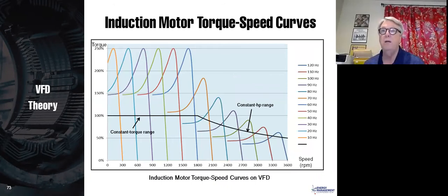Now, I don't have time to get into this too much, but above base speed, the whole torque speed curve tends to go down. So it goes down as the square of voltage, because the torque capability, that whole torque curve, is proportional to the square of the volts per hertz, approximately. And so just wanted to show you what a graph of that would look like.